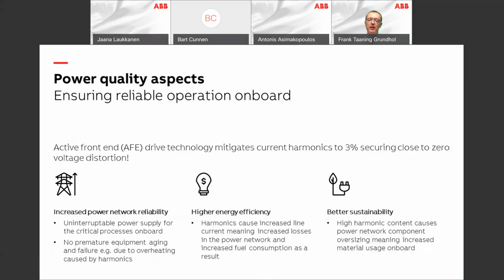What we have done is we've developed solutions with active front-end technology that actually reduces the current harmonics, which is the electrical noise on the current level, to 3%, and that the current is actually what drives the voltage distortion. When you only have 3% current distortion, your voltage distortion is close to zero. So by applying this, especially on the bigger loads, you avoid any risk of exceeding the classification company's requirements and thereby also avoid the requirements for installing additional filtering. When you don't have to install additional filtering, you also save space that can be used for other purposes.